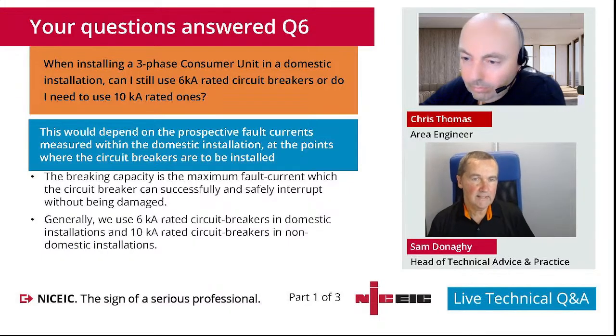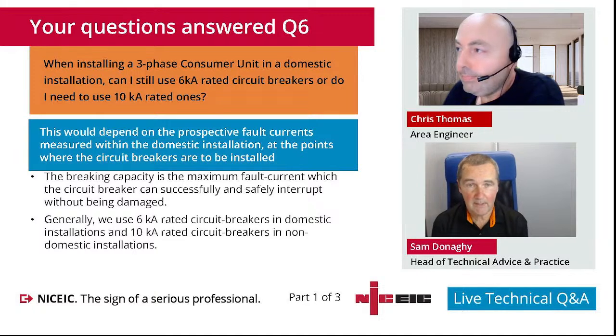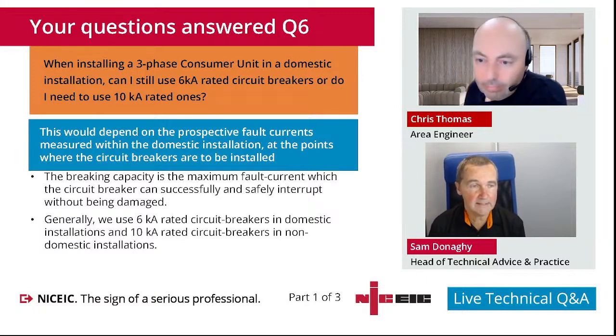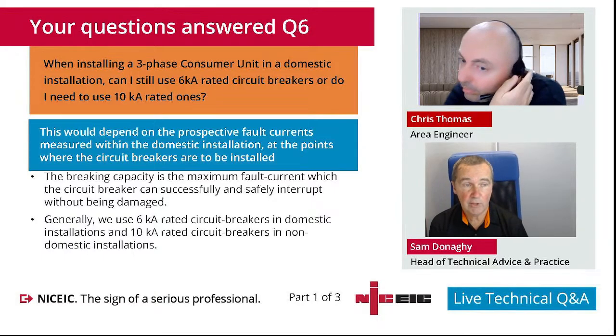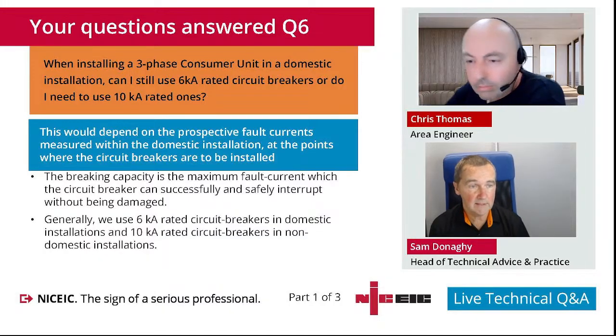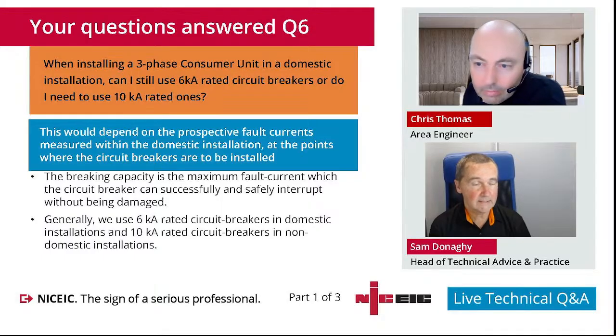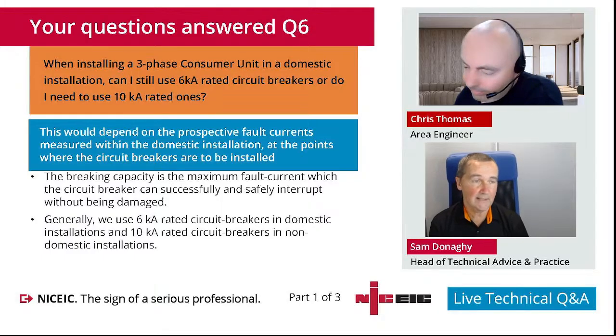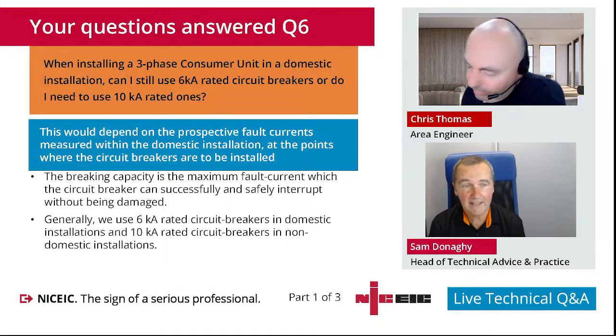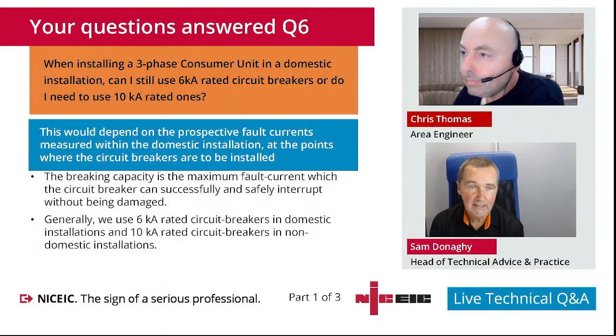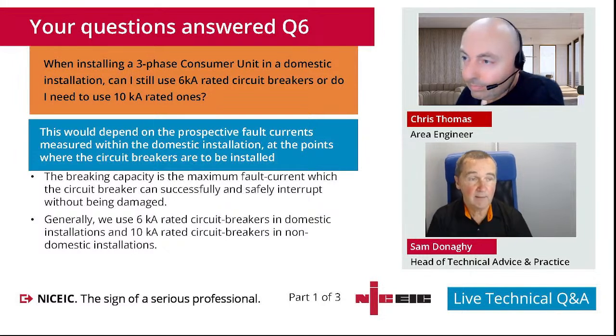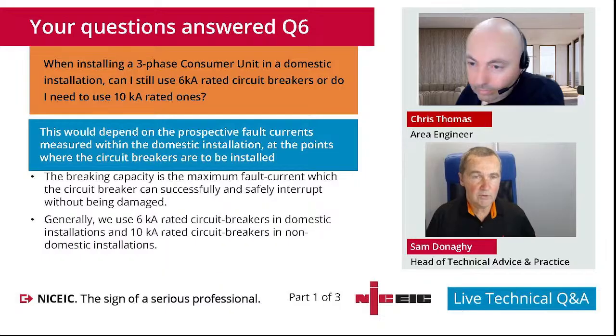So, when installing a three-phase consumer unit in a domestic installation, and myself and Chris were talking offline about this, seeing that more common, as Chris said, in particular where there's large amounts of renewables, and certainly in areas where we've now got electric boilers, perhaps aircon included, as well as battery storage, solar PV, a heat pump. So, when installing a three-phase consumer unit in a domestic installation, can I still use 6 kA rated breakers, or do I need to use 10 kA, which we normally associate with three-phase because it's a larger installation? What's our thoughts there, Chris?